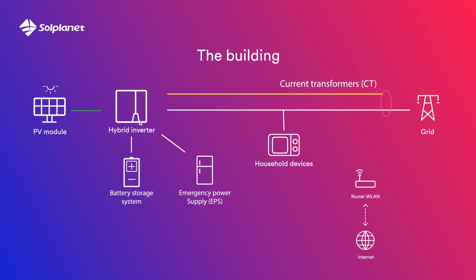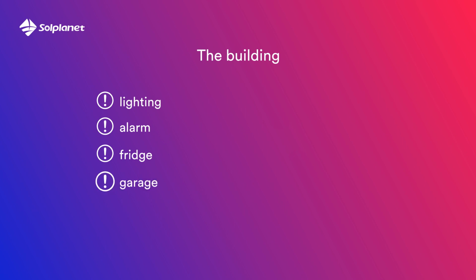This is what a properly connected inverter looks like: PV modules, hybrid inverters, energy bank, load on EPS, load on grid, and very important, current transformers. To the backup output we can connect the most important devices in the building, for example, lighting, alarm, fridge and garage gate.